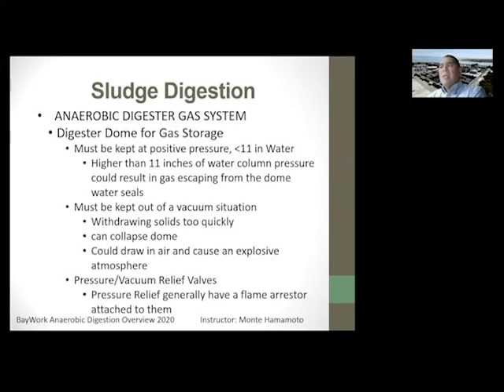The other thing is you must keep them out of a vacuum situation. Remember, this is a closed tank, so if you pull the contents out too fast, you can create a vacuum, and that dome lid — guess what — now it's like a bad souffle, you just caved in your dome, you sucked it in. So you want to make sure when you're withdrawing solids from your digester, you're not doing it too quickly.